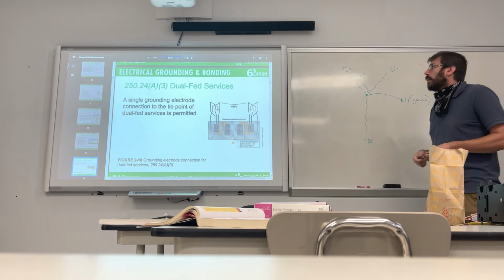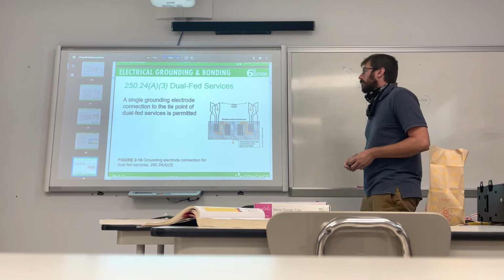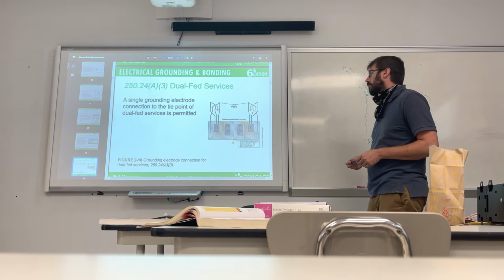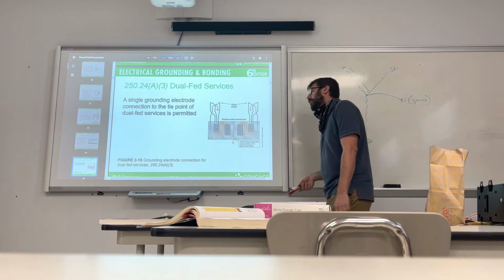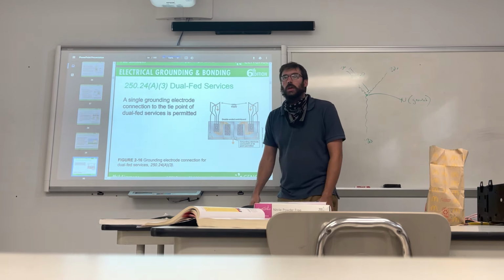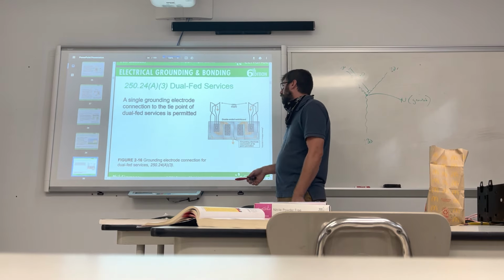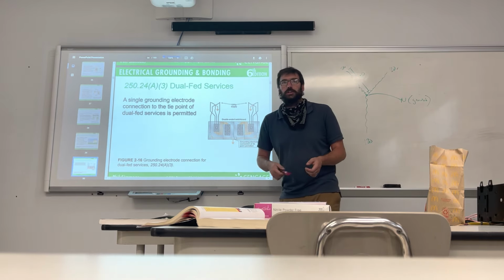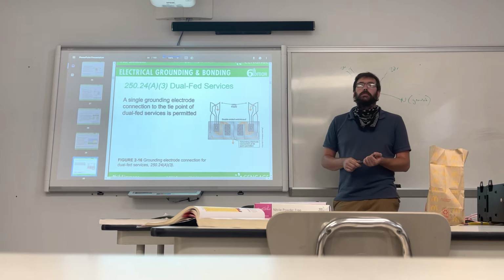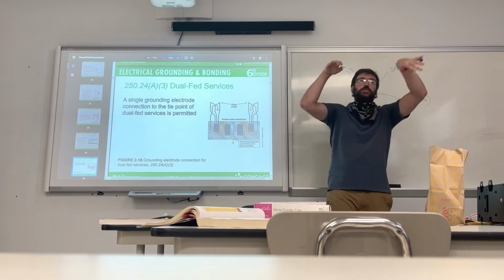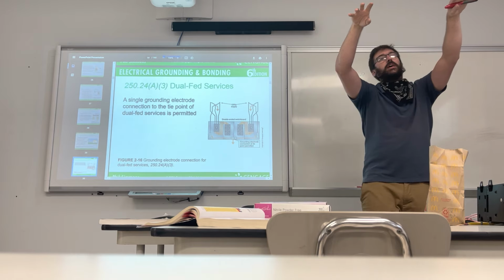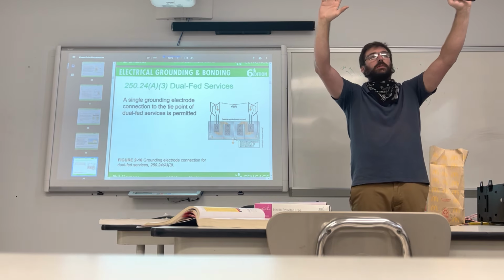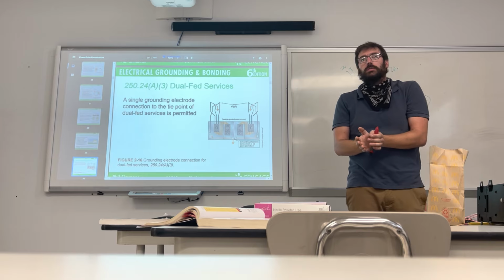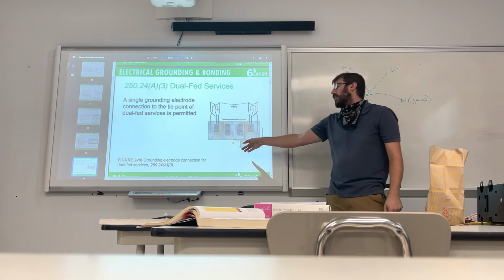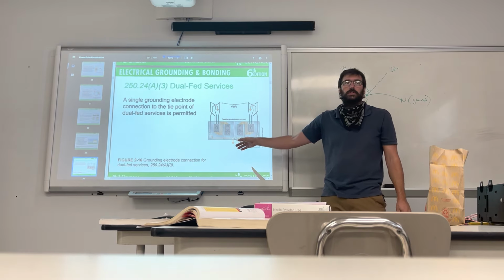Dual fed services: a single grounding electrode connection to the tie point of dual fed services is permitted. Yeah, so this could be two commercial buildings. It could be like a split house, but the way the setup is, it's not for residential. This would be for a building, but you can have two weatherheads right next to each other and two services going into the same weatherheads, and if they're connected to the same building, you can use the same ground. It's not going to be the end of the world as long as you size the ground accordingly. That's going to be the only thing that matters.